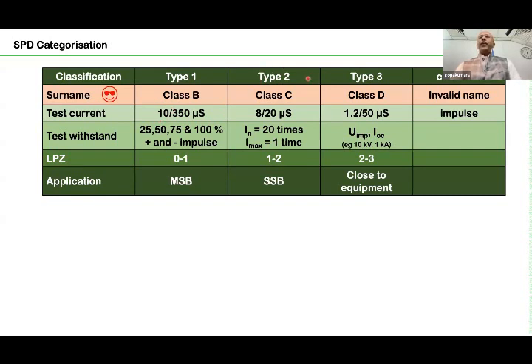Similarly, type 2 SPD was earlier called class C. Class C is not used nowadays; type 2 is used. It is an SPD tested with an impulse current of 8/20 microseconds. Two types of tests are included. One is the nominal discharge current, meaning each SPD should handle 20 times its nominal discharge current. Imax means maximum discharge current, which it has to withstand one time. These are the impulse wave shapes. Now LPZ is a lightning protection zone, 0 to 1, 1 to 2, 2 to 3. So basically these are the classifications.